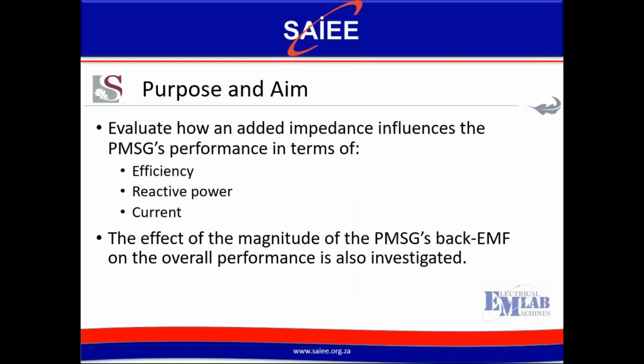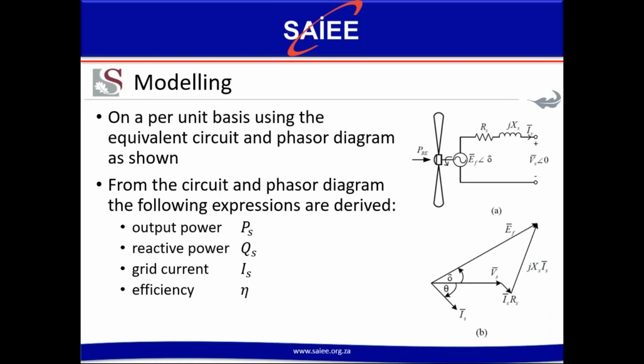The purpose and aim of this paper is to evaluate how an added impedance influences the generator's performance in terms of efficiency, reactive power, and grid current. The effect of the magnitude of the generator's back EMF voltage on the overall performance is also investigated. The modeling is done on a per unit basis using the equivalent circuit and phasor diagram as shown. From the circuit diagram and phasor diagram, expressions for the output power, reactive power, grid current, and efficiency can be derived.